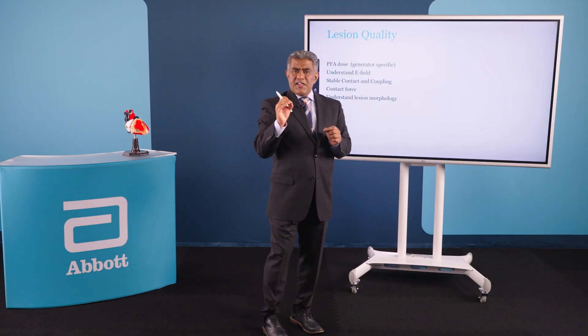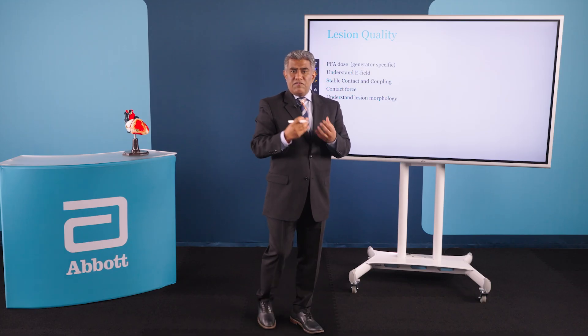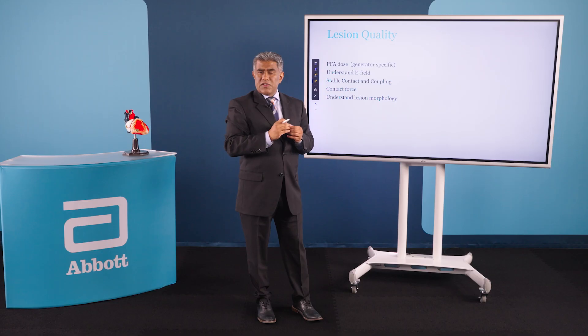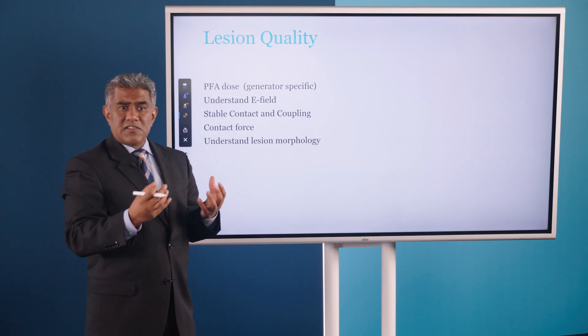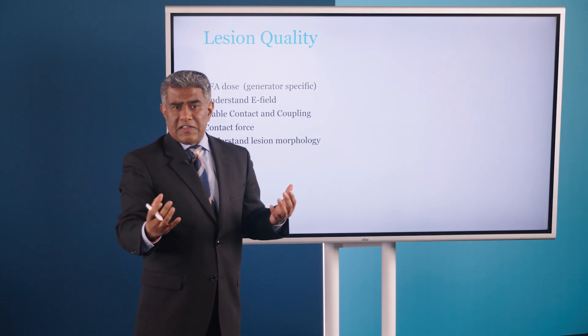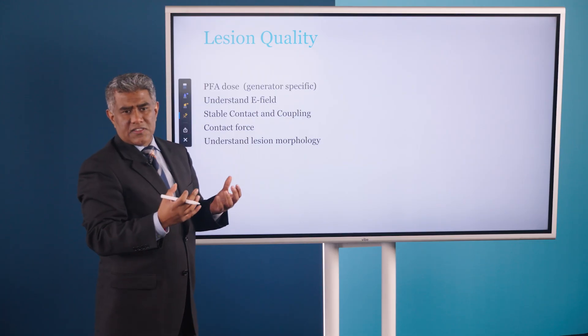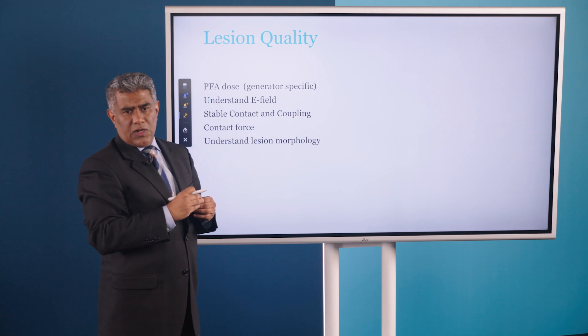What I've said is that lesion quality depends on PFA dose, which is waveform and generator specific. We need to understand the electric field, the importance of stable contact and coupling, and contact force with smaller footprint catheters. We need to understand the lesion morphology, which may not always reflect the electric field. These are the ways you can maximize lesion quality for any catheter you're using in the world of PFA.